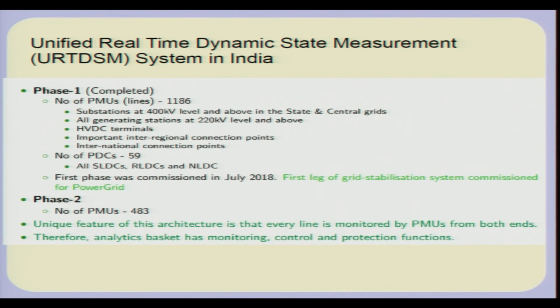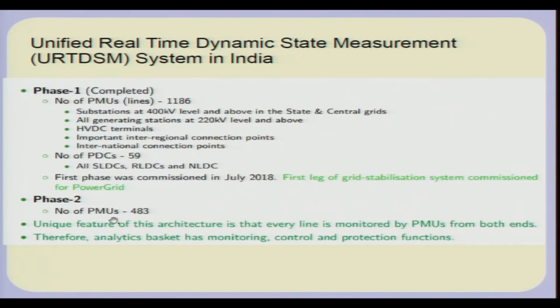In fact, there is a project being completed in India. Phase 1 is completed, where more than 1,000 such phasor measurement units have been put at various substations and generators, and all this data has been collated using PDCs, which are phasor data concentrators, which receive all this data, collate it, store it, and pass it on for some analytical use. A few more PMUs are also being installed as a part of phase 2, and every line is being monitored by PMUs at both ends.